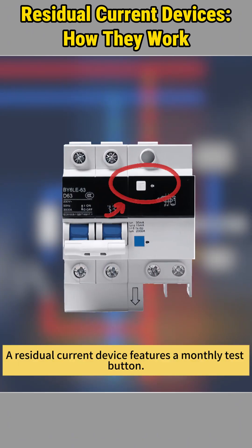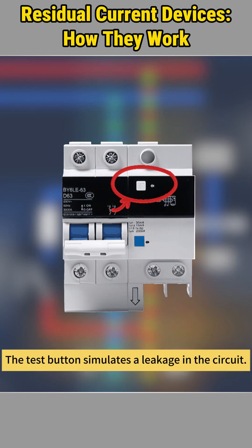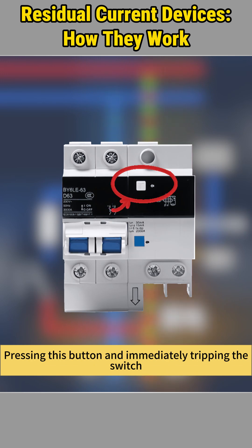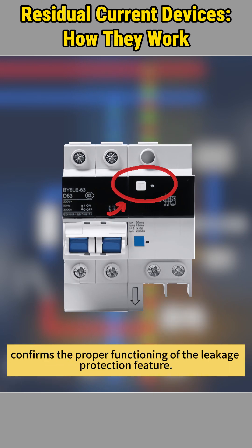A residual current device features a monthly test button. The test button simulates a leakage in the circuit. Pressing this button and immediately tripping the switch confirms the proper functioning of the leakage protection feature.